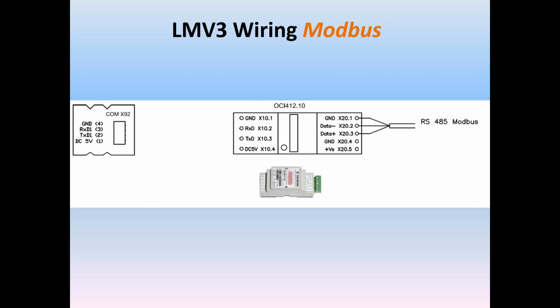If you're going to run Modbus for a touchscreen, BMS, lead lag systems, you would have to add the OCI 412 module. This is where you would connect your building automation or any Modbus device, RS485. It comes with a cable provided with the OCI that would plug into the LMV3 X92, and the green plug would go into the OCI.